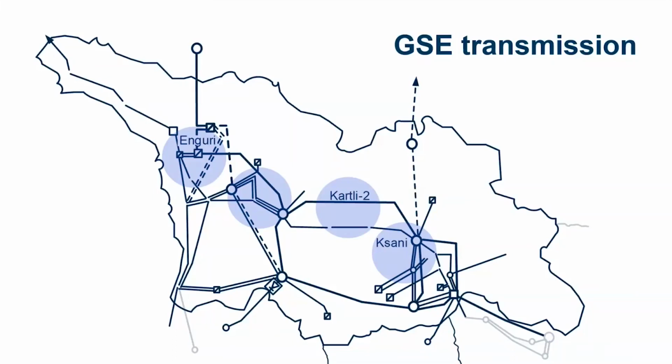Georgia's blackout-brownout history has shown that the power system can become unstable in case of any major contingency event, such as loss of a major transmission line. Angular stability issues resulted in catastrophic events experienced by the power system in previous years. GSE implemented a RAS solution starting with decentralized and finally moving to a centralized approach. Currently, both centralized and decentralized RAS are active. Decentralized RAS will only take action if centralized RAS is not available.